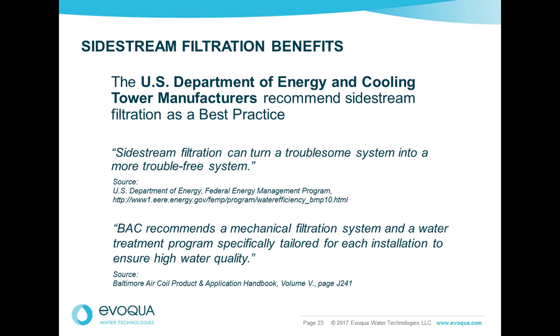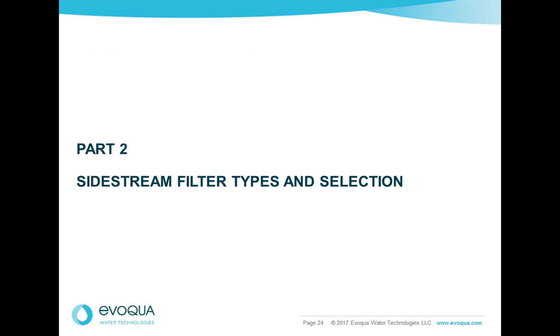Sidestream filtration has been indicated by the U.S. Department of Energy and cooling tower manufacturers as a best practice. Baltimore Air Coil recommends mechanical filtration and water treatment specifically tailored for each installation. And you really have to look at the installation and the needs of the installation to decide what's the best sidestream filter. And your equipment manufacturer is a good place to start.